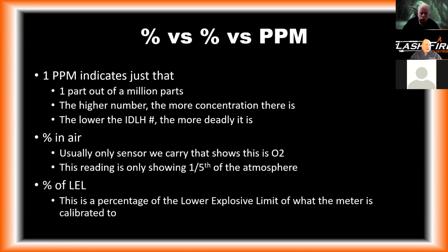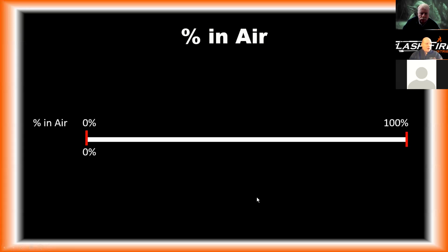We have to remember that the other 4/5 is changing as well. And then percent of LEL, this is the percentage of the lower explosive limit of what the meter is calibrated to. So we have to understand our meters are calibrated to methane, and this percent of LEL, while it can be used to read any combustible gas out there or any flammable gas out there, is only accurate on a 1-to-1 ratio to the gas that it's calibrated to, which is natural gas or methane. And I'll explain that in a couple slides as well.